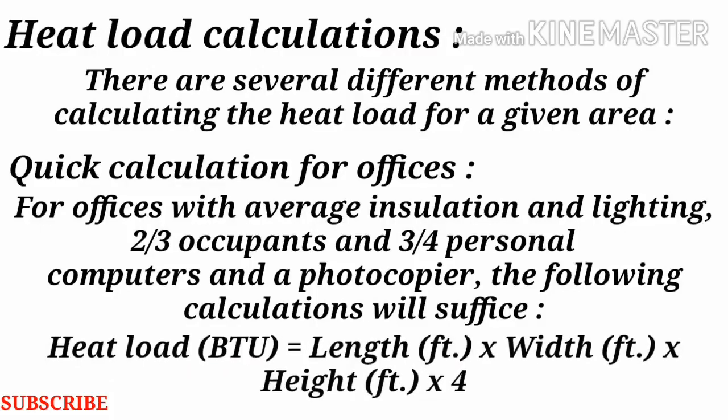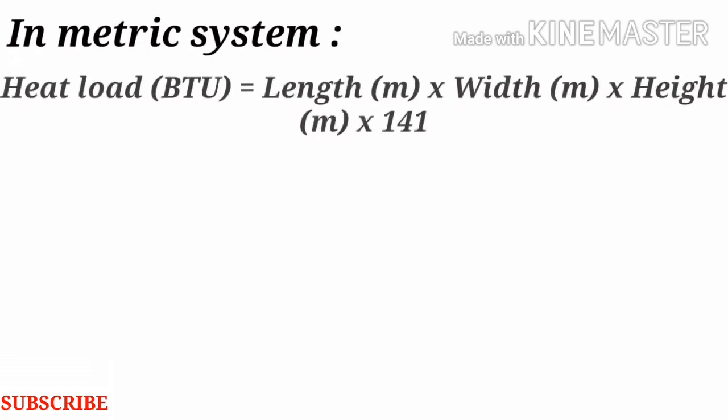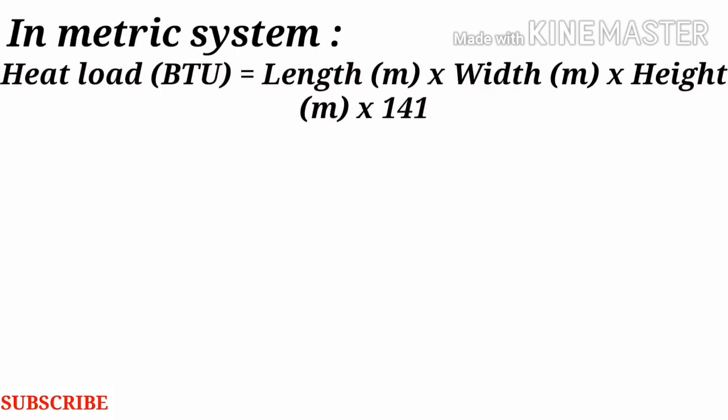Heat Load (BTU) equals length in feet multiplied by width in feet multiplied by height in feet multiplied by 4. In the metric system: Heat Load (BTU) equals length in meters multiplied by width in meters multiplied by height in meters multiplied by 141.